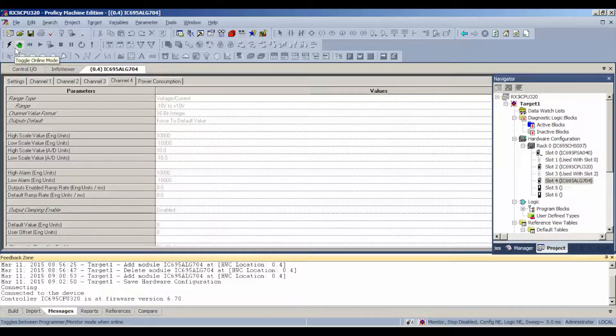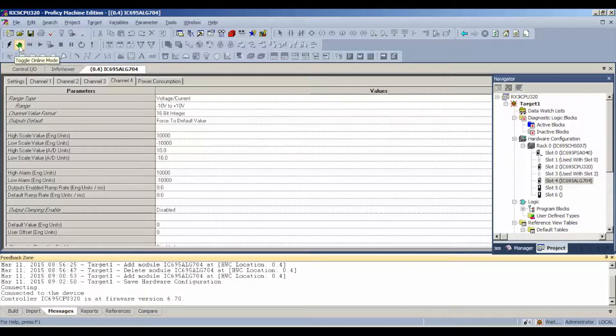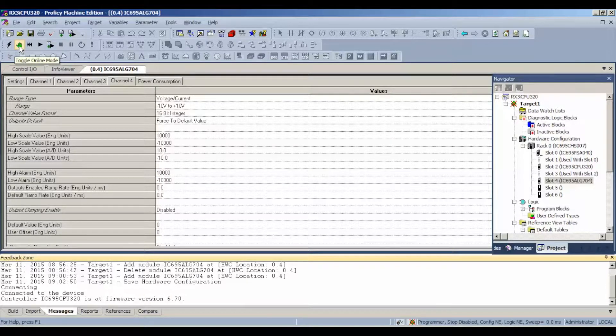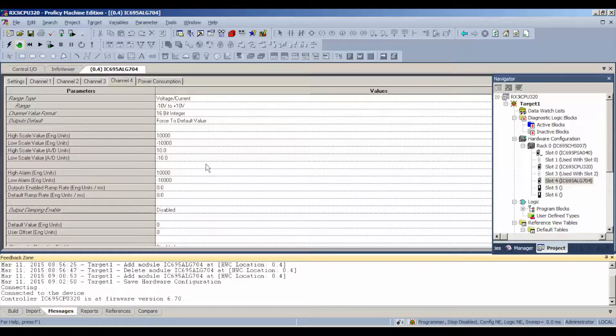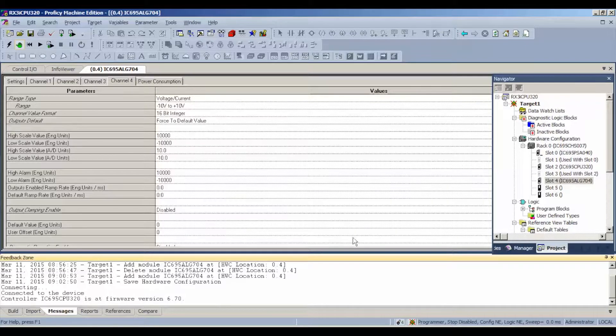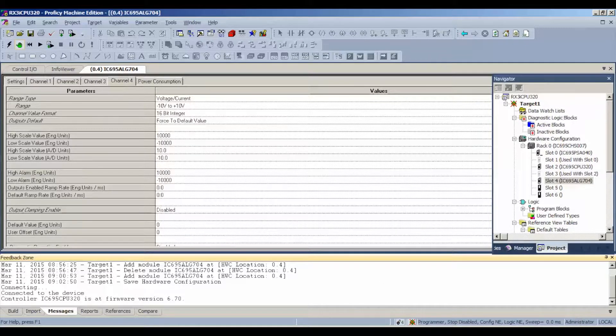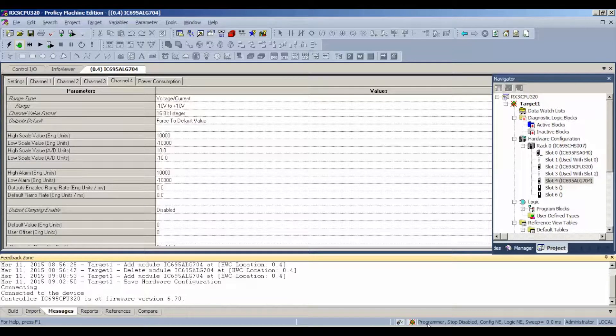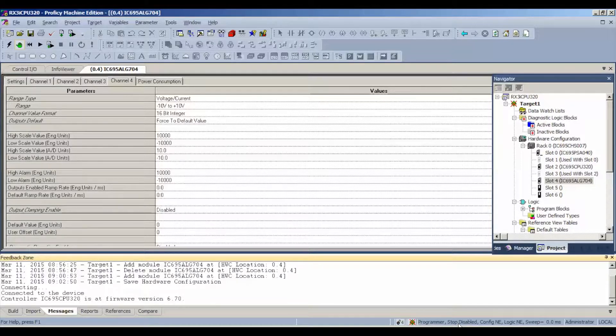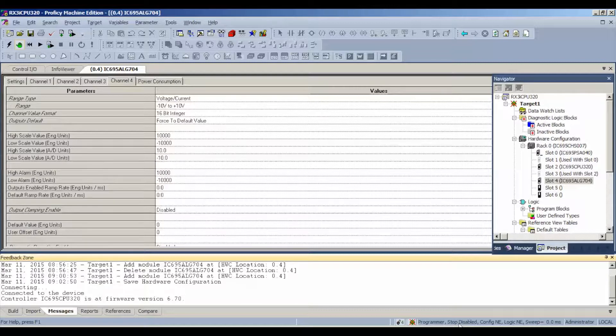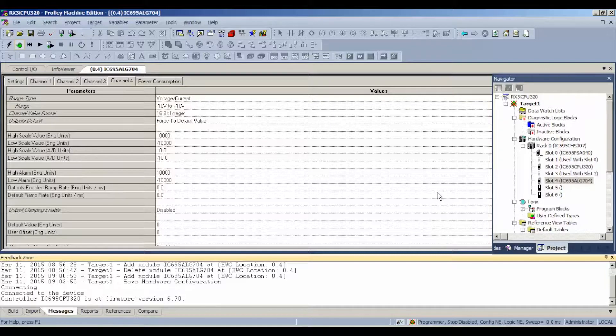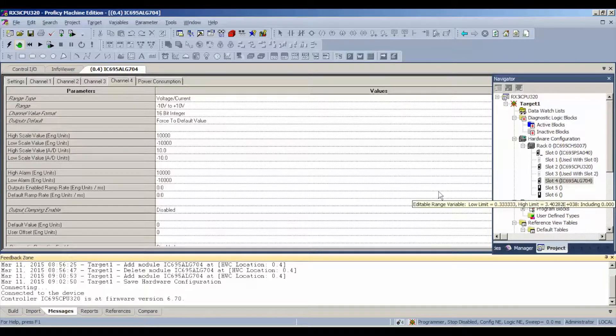Stop here for a second, follow my arrow. Note the status of the processor in this bottom portion here, this information is in programmer mode. The outputs are stopped and disabled. The configuration is not equal and the logic is not equal. According to the processor, it's not equal because the processor was handling a different task before we've asked it to test this analog card.